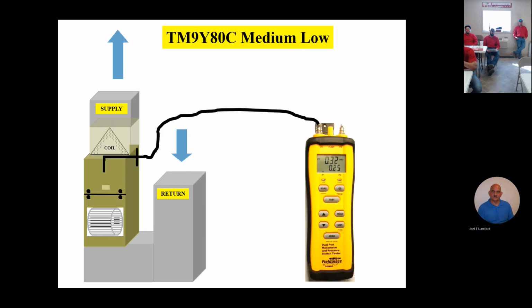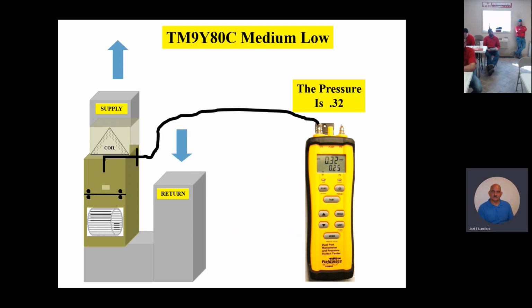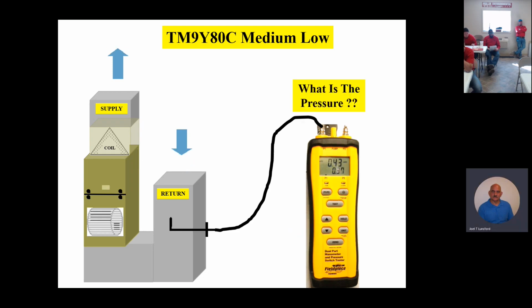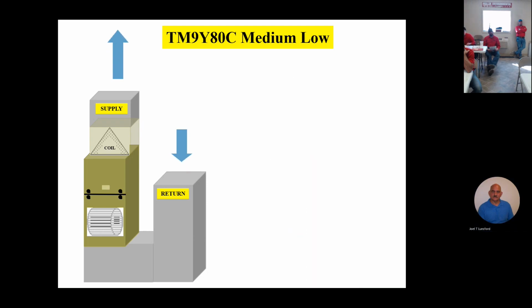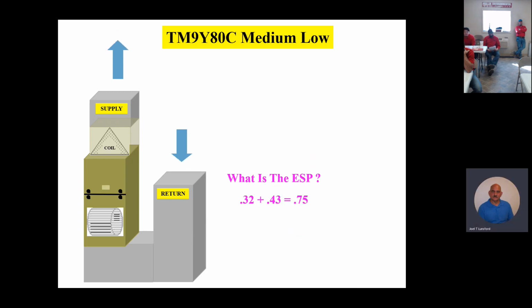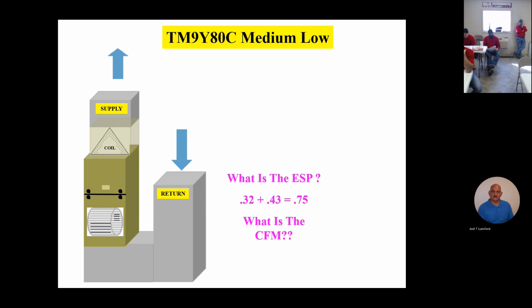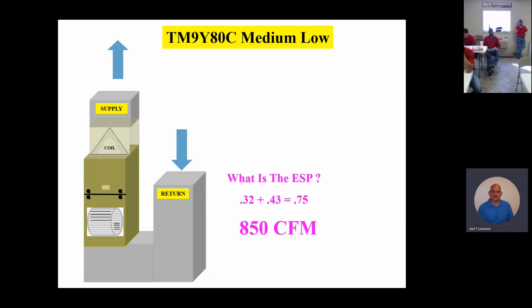Okay. Here's a TM9Y 80C, medium low speed tap. And we've got a 0.32 on the supply and a 0.43 on return. So let's add those up. What's our total static? 0.75. Okay, 0.75, which is getting pretty high, isn't it? And so we're on medium low speed tap and we're still running 0.75. What's our CFM? 855. Okay, good. I had 850, close enough.